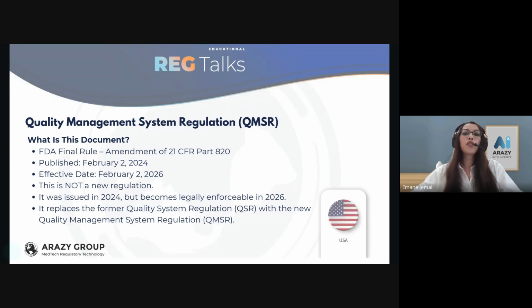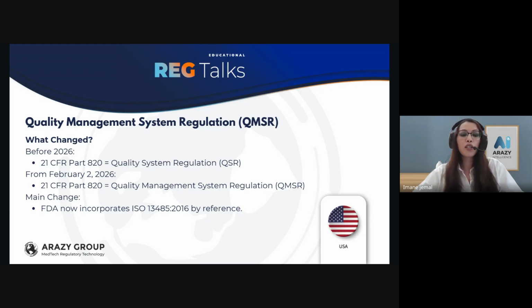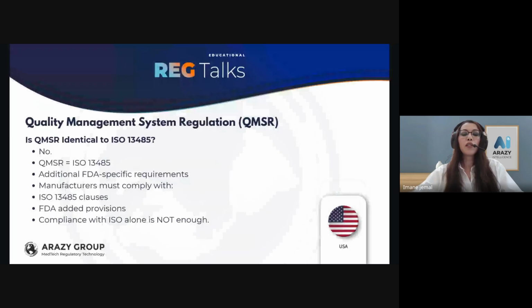The major change is structure, not conceptual. Previously, FDA had its own standalone quality system regulation. Now it directly incorporates ISO 13485 2016. Let's see how. So this is very important. Although FDA incorporates ISO 13485, compliance with ISO certification alone does not automatically mean compliance with the FDA QMSR. FDA added certain requirements to align with the US law.